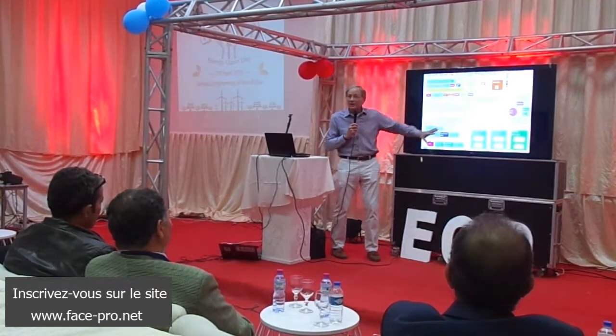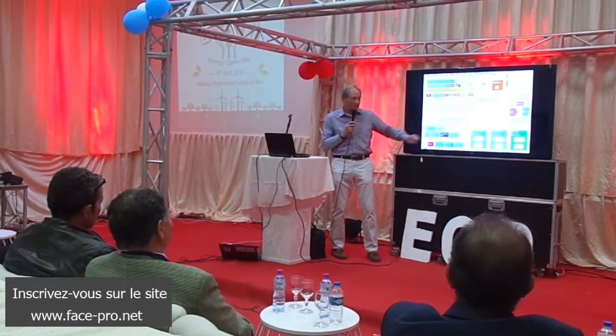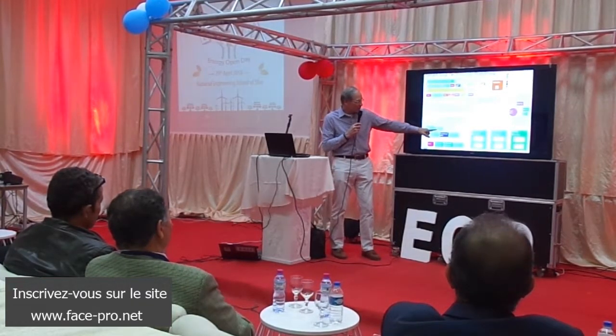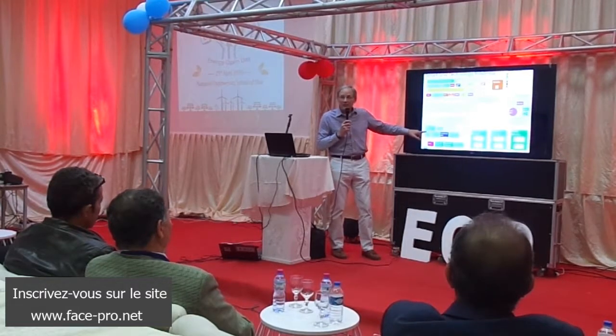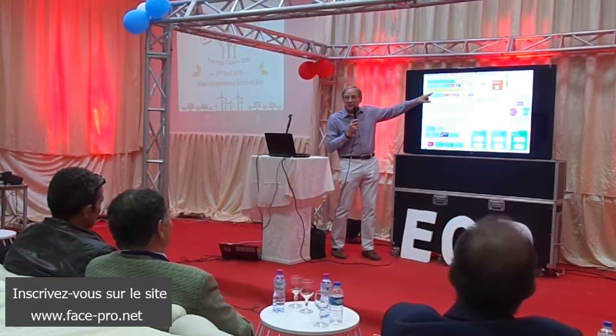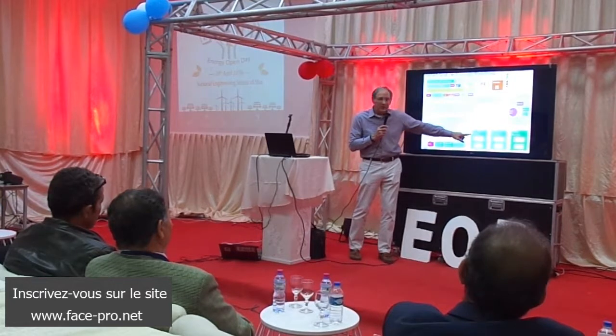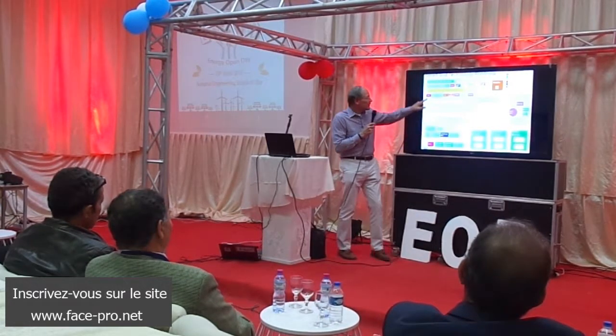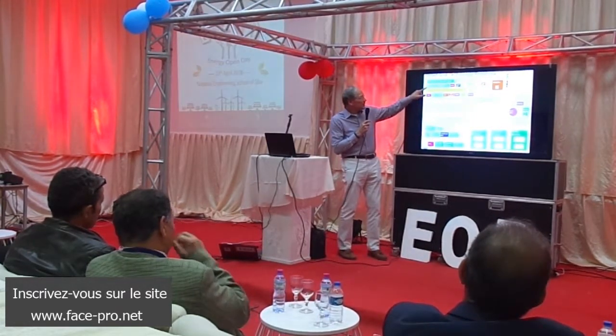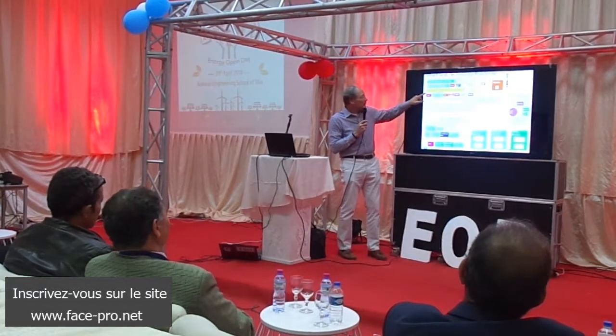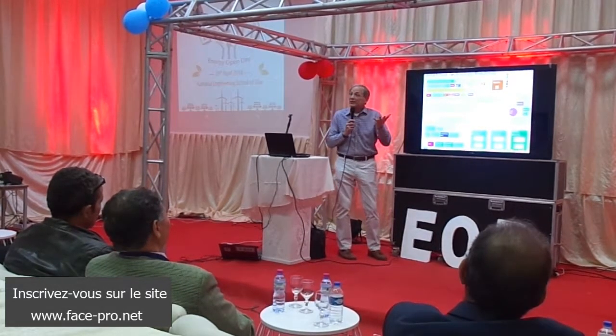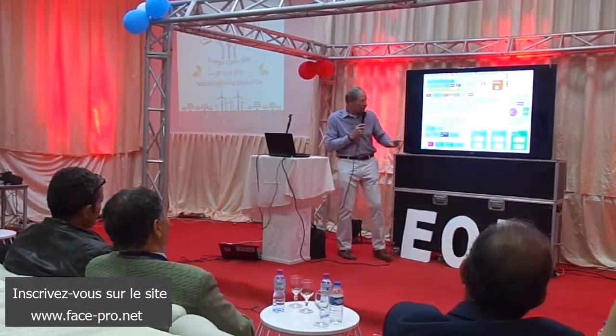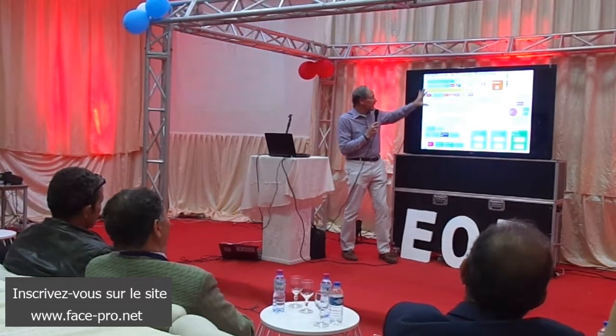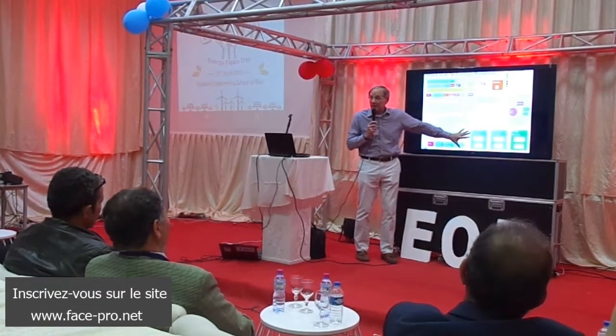I'll show you that in a minute—we call them grid edge controllers. We can run applications at the substation level or at the control center level. I need switches on the feeders because the logic up here handles fault detection, isolation, and restoration. When I detect a fault and want to isolate it, I need to open a switch on each side of the fault. That's what these switches do—here's the logic and here's the equipment on the feeders.